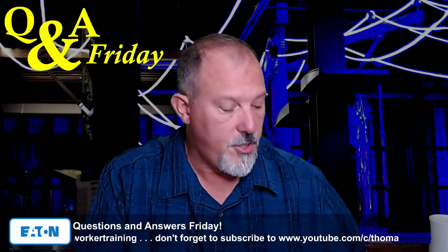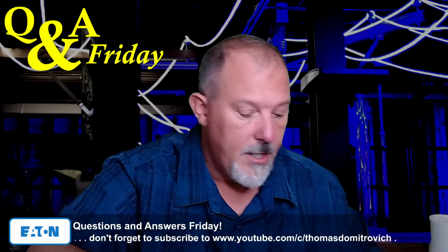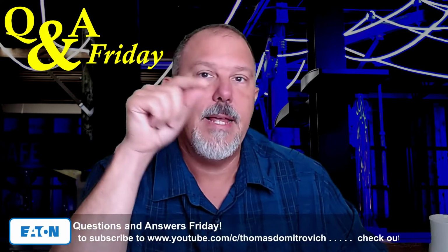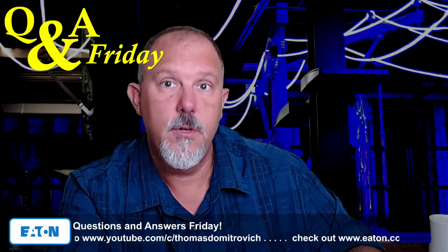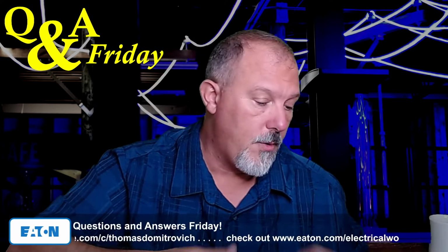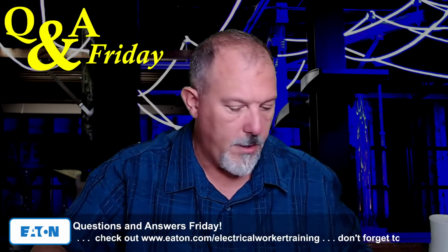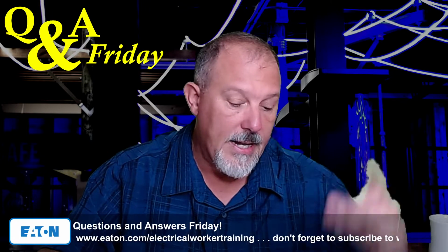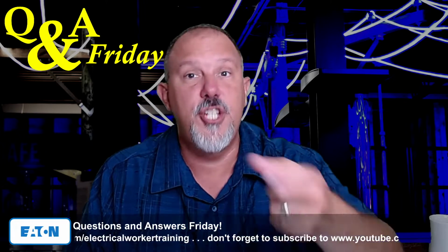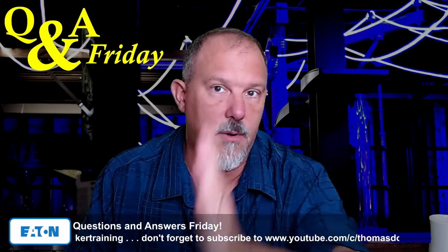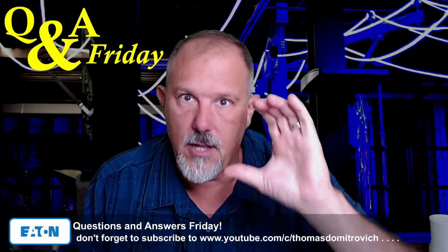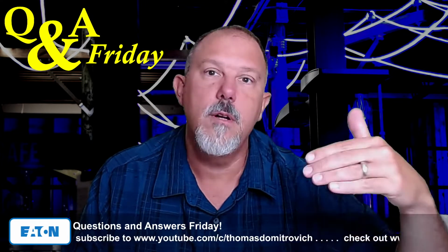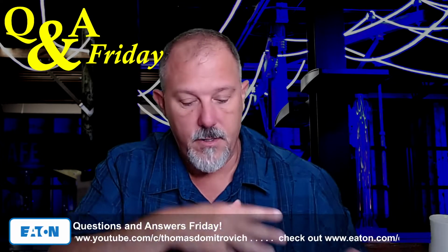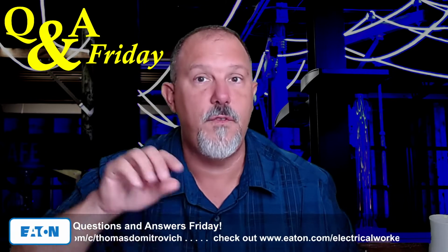What I would say is when you look at 240.87 and you want to know where does it apply, you would say if you have a circuit breaker that is 1200 amps rated, 1200 amps and above, or can be adjusted to. So how do we know about the rating? We go back to 240.6. Yep, 240.6 gives us the standard ampere ratings. And even if I have the locked cover on there, if I can adjust it up, regardless of whether or not it's locked, if it's a 1200 amp frame set at 600 amps and it's a locked cover, you can technically say it's rated for 600 amps. But 240.87 says or can be adjusted. So if you can adjust that, then you still have to apply 240.87.